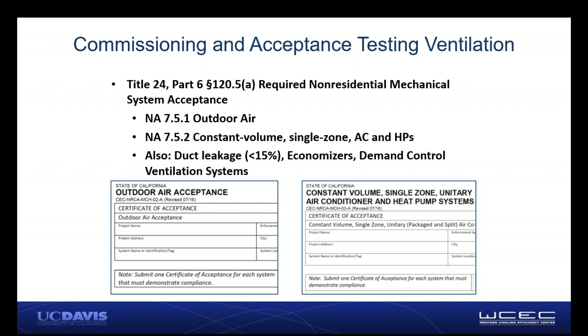I want to talk a little bit about what acceptance testing looks like. This is one of our engineers measuring the outdoor air flow rate going into the classroom through the outdoor air intake. What needs to happen is you measure the outdoor air rate for each unit and confirm it's within 10% of the design—likely that 450 number I mentioned earlier, though it could be a little different for different applications.